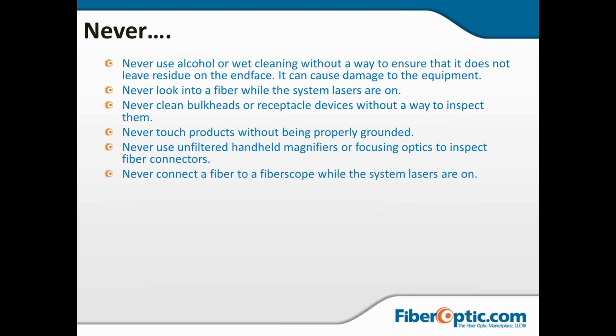Never connect a fiber to a microscope while the laser is on. That's also talking about the probe. If you shoot laser into the probe, you may damage the probe. I'm going to tell you the truth - I'd rather throw the probe against the wall than get spots in my vision. So if I'm ever uncertain, I'm going to plug it into a probe, not a microscope. You always want to be diligent, but if a mistake happens, I want it to happen to the probe, not to my eyeball.